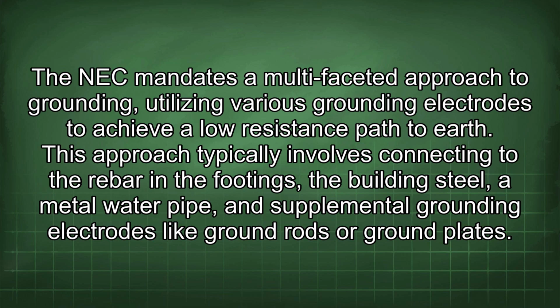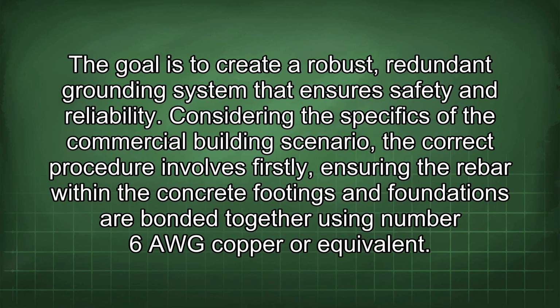The NEC mandates a multifaceted approach to grounding, utilizing various grounding electrodes to achieve a low resistance path to earth. This approach typically involves connecting to the rebar in the footings, the building steel, a metal water pipe, and supplemental grounding electrodes like ground rods or ground plates. The goal is to create a robust, redundant grounding system that ensures safety and reliability.